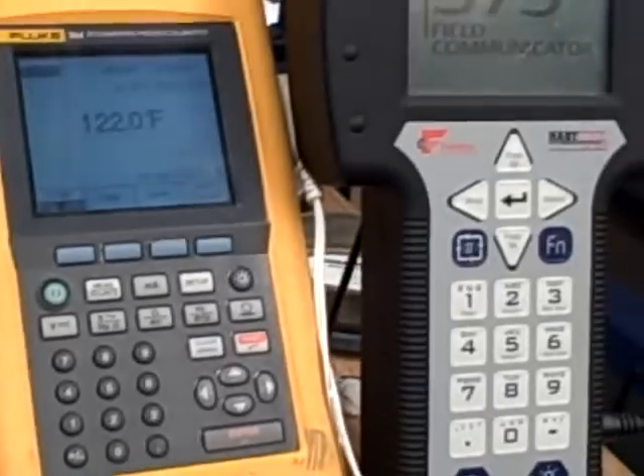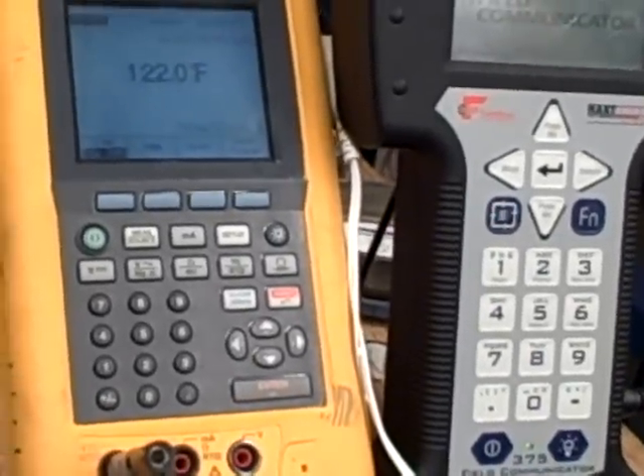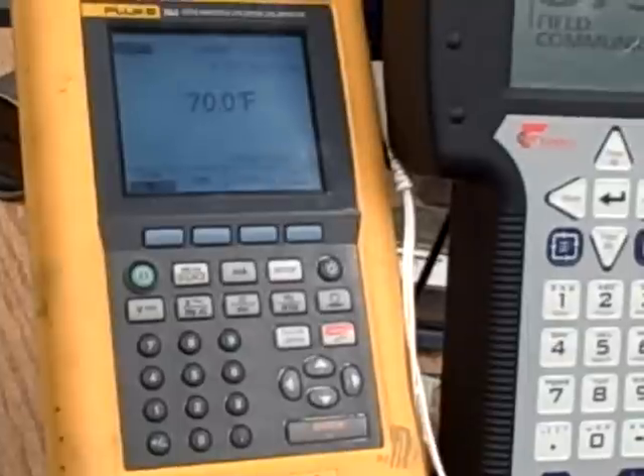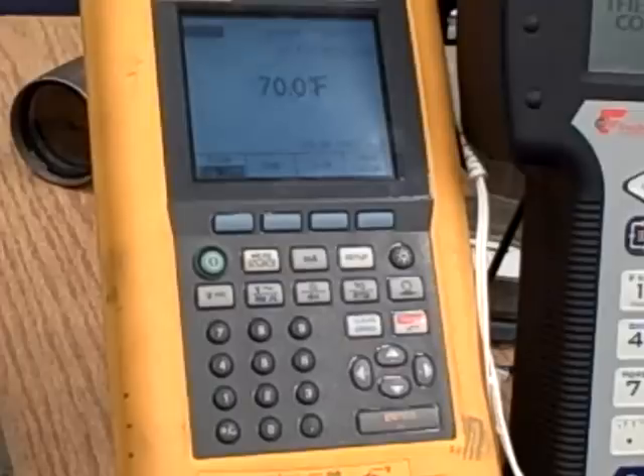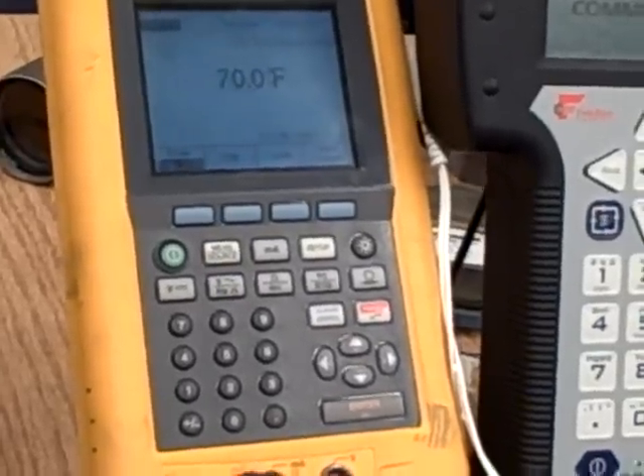So 20 to 120, halfway in that range would be 70 degrees. I'll set this to 70 degrees Fahrenheit. Now we should be inputting a signal to the transmitter to drive it to 12 milliamps. And that's how you set up the Fluke 744.